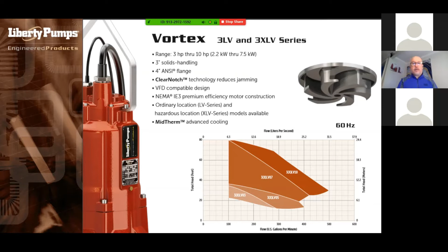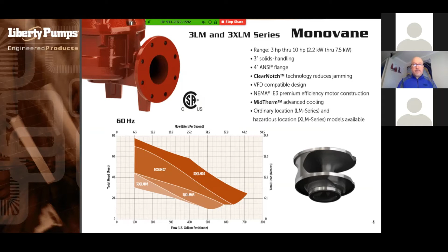Here's the mono vane series, similar bullets here: 3 through 10 horsepower, 3-inch solids handling, 4-inch ANSI flange, clear notch design, and mid-therm cooling. They all have the shaft grounding brush, so that's a VFD compatible design. So the mono vane pump is getting us out to over 700 gallons per minute and heads up to about 78 feet or so. So we're getting into some pretty nice flows and heads for a 3-inch solids handling pump. And then a 2-vane version as well, a closed 2-vane.